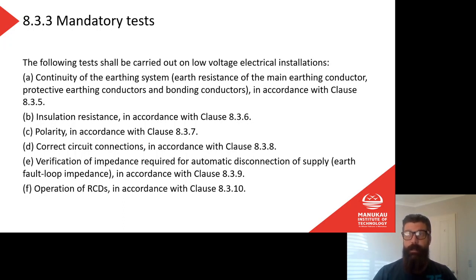How do we do that? We need to test that all of those conductors are continuous. That means that they're connected at one end and connected at the other, and that we have a good circuit in between. An example of not continuous would be if somebody had cut one of those wires. So if I test the earth wire at the socket and I test the earth wire at the switchboard, I should have a circuit in between. There should be one continuous wire running through that. If I do that test and that is not a circuit, or the resistance is too high, then I know something has gone wrong. There's a fault in there.